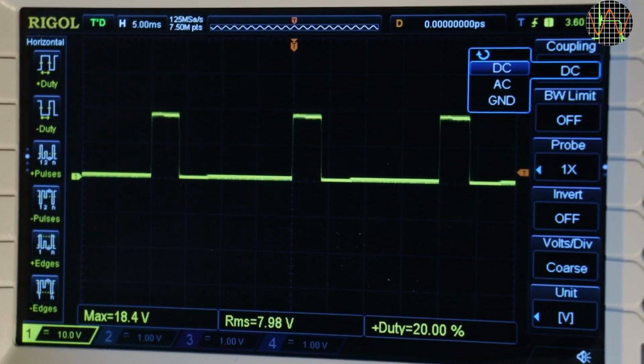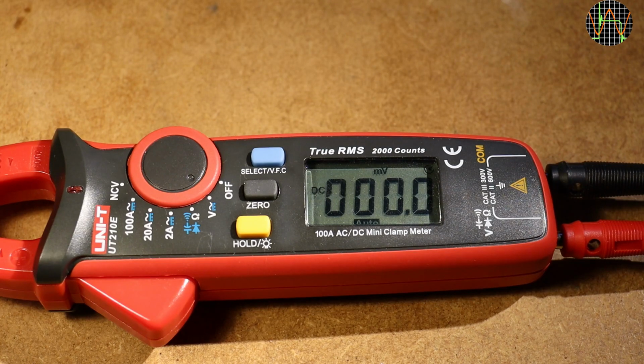It's probably a good idea not to use the full 6000 count when measuring AC volts or current with unknown waveforms. There are three known issues or quirks with the 0 button on the UT210E. The first, using 0 stops auto range from working. I'm demoing this with DC volts, but the issue applies to other modes as well. You can see that when I go above 6 volts, the meter switches range as expected in 6000 count mode.